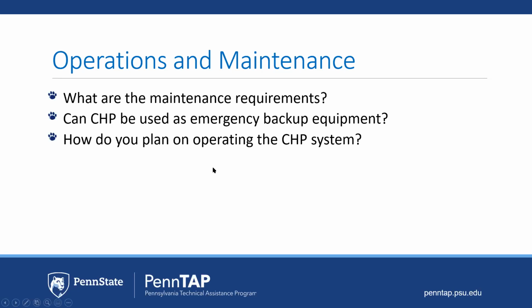I'd like to support that, Rizwan—this is Tom Crooks. You're planning on 90, 93, as high as 96 percent capacity factors on this equipment, so it's already operating. The extent to which it can be called on in an emergency, it's already running. You'd need fuel storage possibly, and this is where your codes come in, requiring diesel backup with diesel fuel storage able to come up within a certain number of seconds. So to me, you're operating these things all the time—if the question is how you'd operate it more in an emergency, I don't see it as standby power. It's already operating.